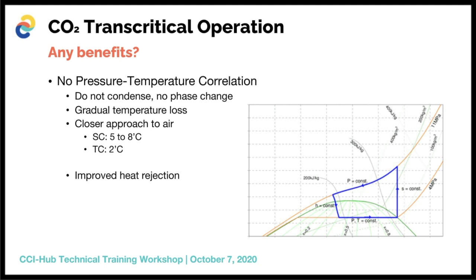And that gives you the ability that you can have a closer approach when you're working in a transcritical mode. So for instance, mostly you will find in a subcritical manner when you are condensing a refrigerant that you will allow for a temperature difference of about 5 to 8 degrees Celsius between the refrigerant and the ambient air conditions, where with CO2 in a transcritical manner, this is about 2 degrees Celsius only because of the closer approach. So this means that you can still have a lower gas cooler outlet temperature, even at higher ambient conditions. And sometimes the comparison that needs to be done when choosing a CO2 plant in the transcritical region needs to take into account that there is a closer approach. Additional benefits come when you are utilizing this for heating purposes, where you get a very good heat rejection method because of the capabilities and the properties of CO2 in its transcritical state.